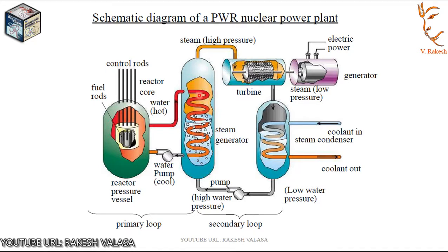After the heat transfer in the steam generator, the cooled water in the primary system is pumped back into the reactor pressure vessel. The pressure on the secondary side of the steam generator is only around 64.5 bar. The feed water evaporates here at around 280.5 degrees Celsius. This produces steam which is then routed through the turbine.